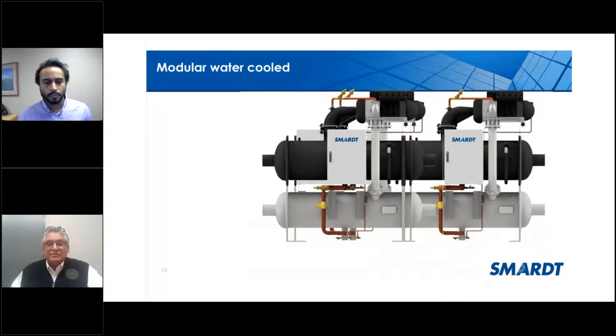How does that happen? If you notice on the diagram to the left, you'll see the machine there, compressor, obviously evaporator, condenser. If you notice it to the right, you'll see a split in the water box, which is right in between the two machines. What you can actually do is add an extended water box on the evaporator and the condenser and not install the compressor till later. It's almost like a puzzle set. You can put the extended evaporator and condenser in now or wait till later, and install both of those to the existing machines that are there now. So now you have a linear type approach in modular versus just straight through versus parallel. Actually a pretty good application. So something no other manufacturers can do, quite honestly, based on their design.